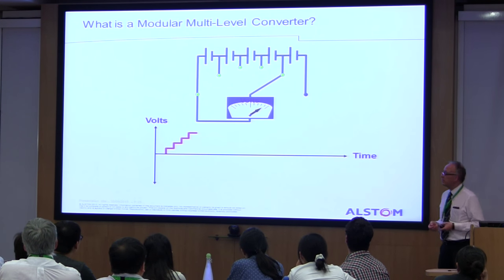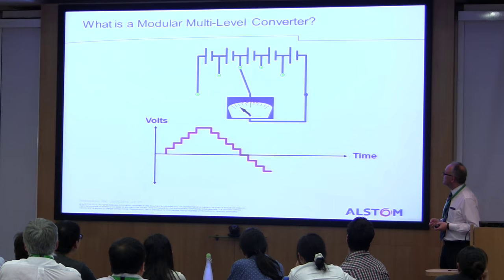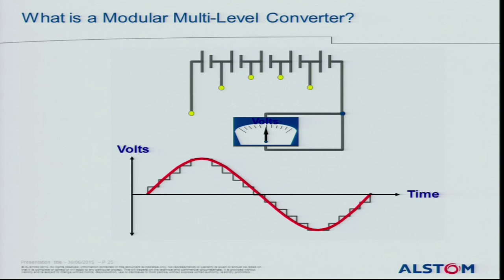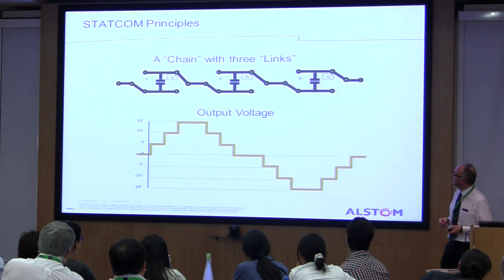What is a modular multi-level converter? Basically, we have lots of little steps connected all in series, and we build up a sine wave from those individual steps. You need surprisingly few steps to get to a sine wave with harmonic content adequate for connection to the grid. We use switches to represent the IGBTs or power semiconductors, and we can get various voltage steps by interconnecting or bypassing the capacitors.